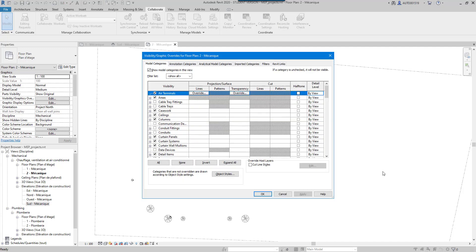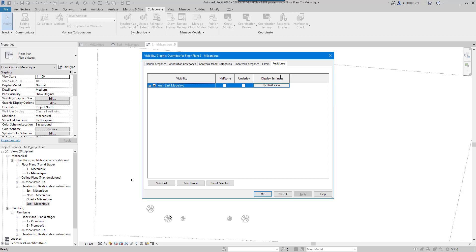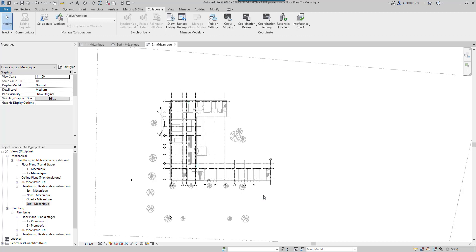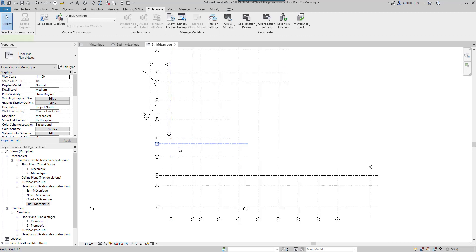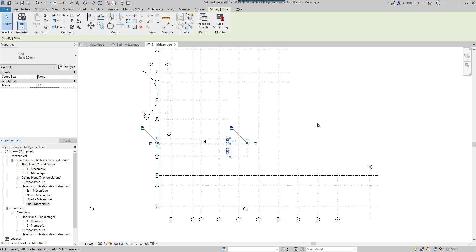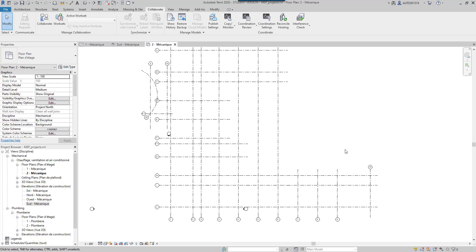Now if I go to Visibility Graphics VV and go to Revit Links here and uncheck the link, I have my own grids. I have this symbol - that means there is a relation between the architecture grid and my mechanical grid. That means if the architect moves his grid, I will have notification for coordination when I reload the link in my MEP project.